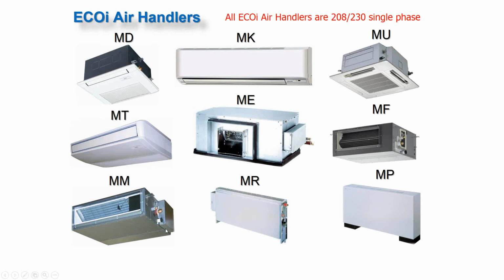Next we have our MM, which is our low static concealed ducted unit. This is low profile for tight ceiling applications. It is not good for long duct runs. The fan in this unit is small, so you cannot put a lot of ductwork on this. You've got to watch your static pressure and the CFMs you need for each space you're using this for.